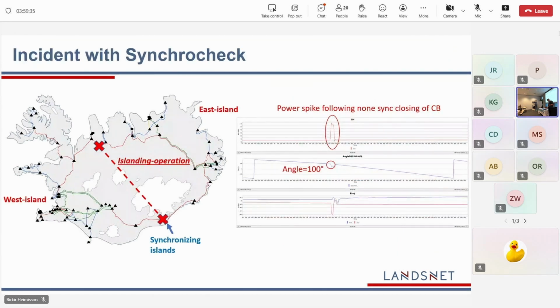Here's an old event we had. After we commissioned one of the stations, we were having islanding operation in our grid, so 2 islands, and we were supposed to close that island, synchronize it together in one of the new substations. And when we went in there and closed the breaker, it closed on a 100-degree angle, leaving a massive shock to our system.